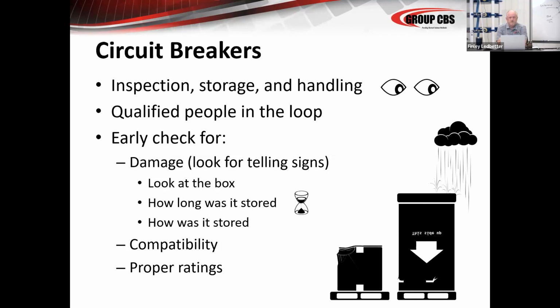Make sure there's qualified people in the loop, not only in the install, not only in the testing and inspection and maintenance, also in the handling of this equipment. This equipment is damaged more often in handling than anything else. We see as much damage in people taking these breakers out of service for testing and maintenance as we see that they're worn or defective or failed in service.